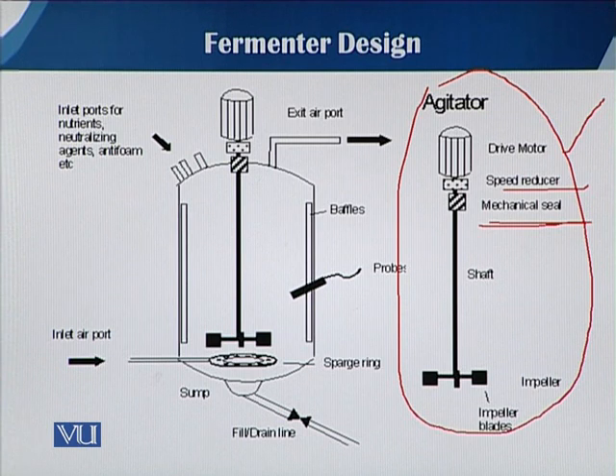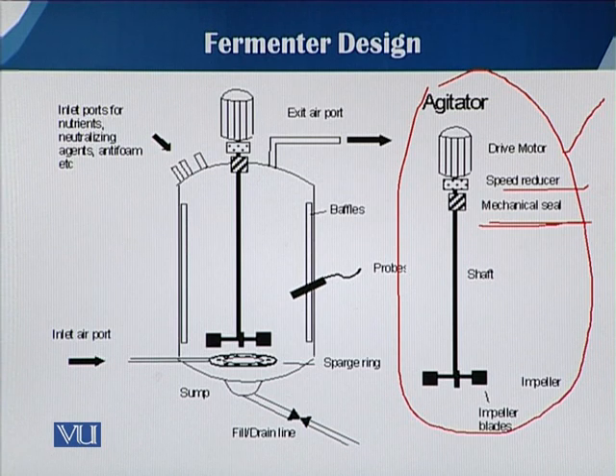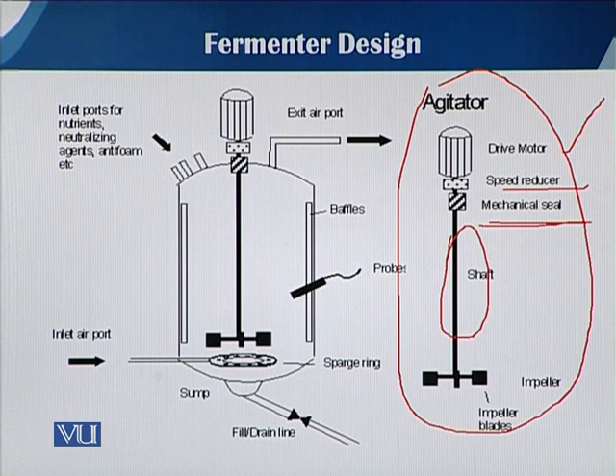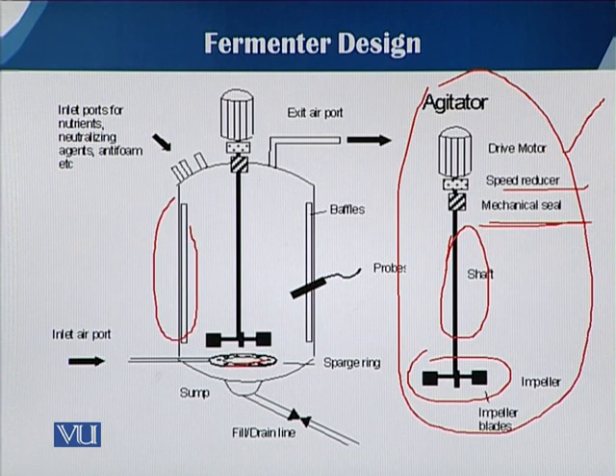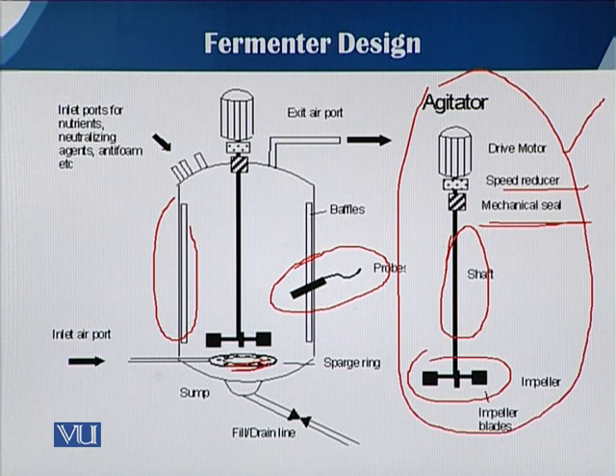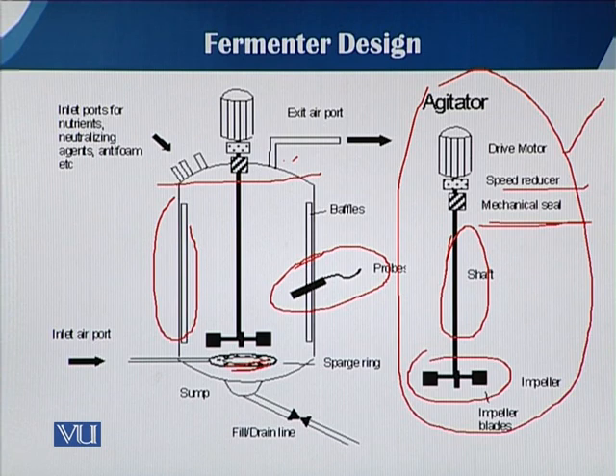The seal in a fermenter is very critical. In laboratory-scale fermenters, the agitation system can be based on magnetic action with no physical link between outside and inside. There is a shaft and impellers, which can have six blades, four blades, or different types of blades. You can also see the baffles and the sparger, and there are different probes such as oxygen probes and pH probes. In some fermenters these are attached on the top plate, while in larger fermenters they are placed on the side wall.